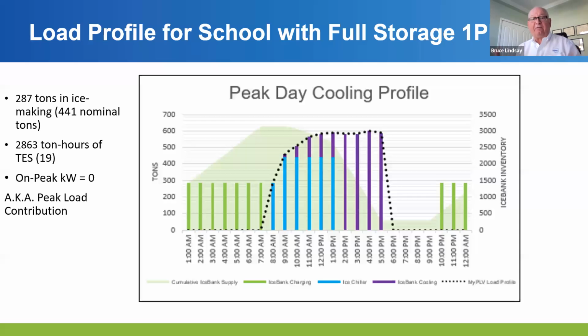This is a pretty confusing graph, but let me walk you through it. The little black dots are the load profile for the conventional chiller, and it tops out at 600 tons. The alternative now is to go to a full storage ice storage system, where I produce the ice shown in green. I start that at 10 p.m. at night, run it till 7, then switch back to running the chiller as a chiller and using the ice to supplement that to meet my load profile. Then at 2 o'clock, I fall into the peak period for that utility, and I shut the chiller down and just use ice. In this case, I was able to downsize the chiller to 441 tons. I had to put in a whole bunch of ice, roughly 19 tanks, but I have a 0 peak kW.